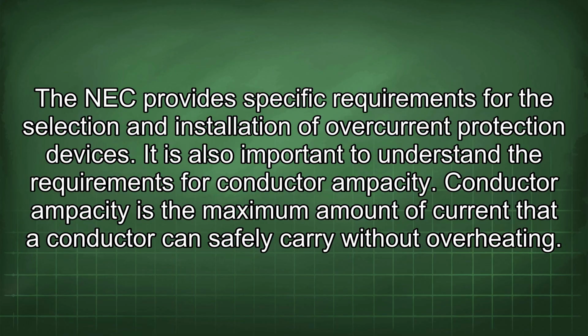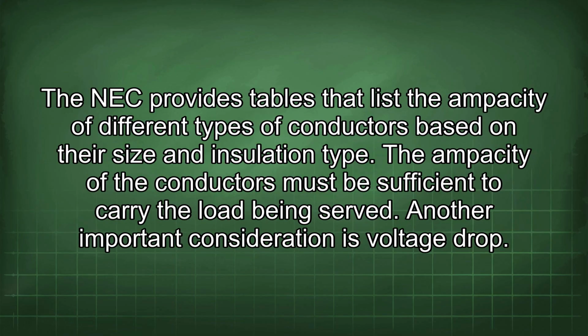It is also important to understand the requirements for conductor ampacity. Conductor ampacity is the maximum amount of current that a conductor can safely carry without overheating. The NEC provides tables that list the ampacity of different types of conductors based on their size and insulation type. The ampacity of the conductors must be sufficient to carry the load being served.